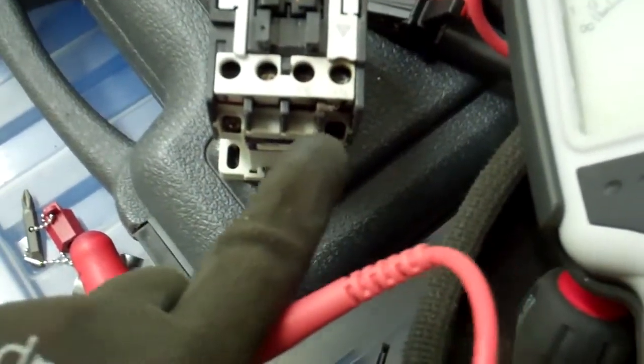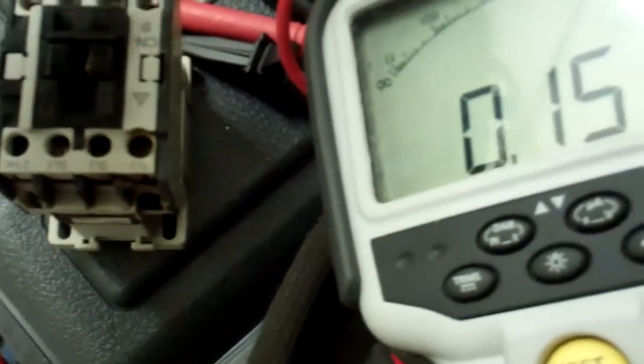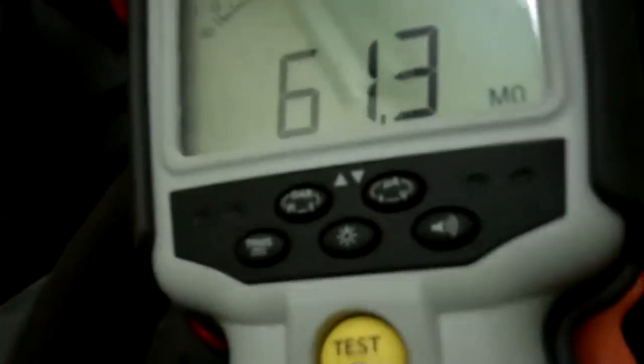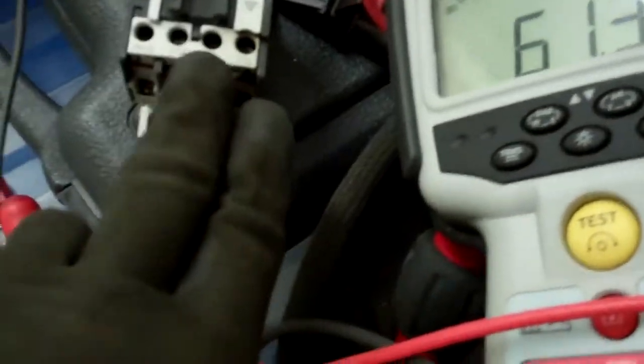That's the contactor. 0.15 megohms, since those two contacts are shorted out. So we'll compare that to the ones on the opposite side. 61 megohms. So we've checked out the two phases.